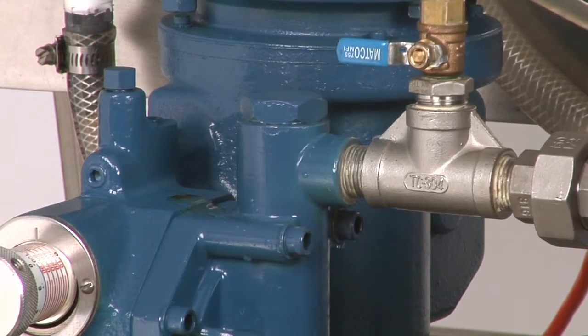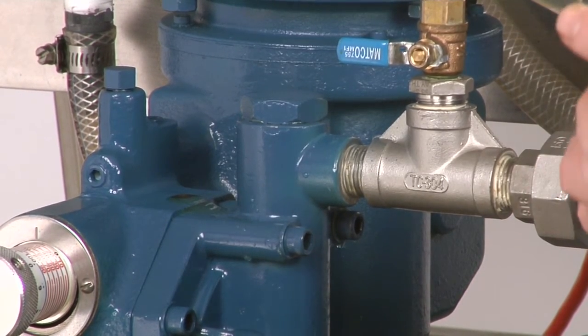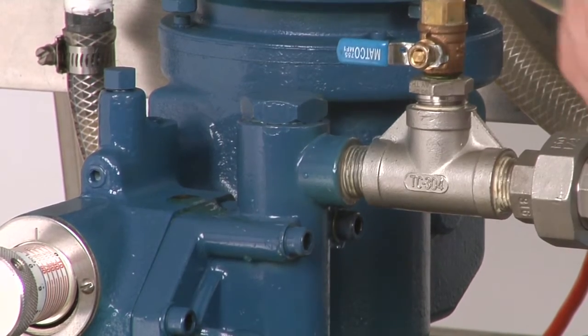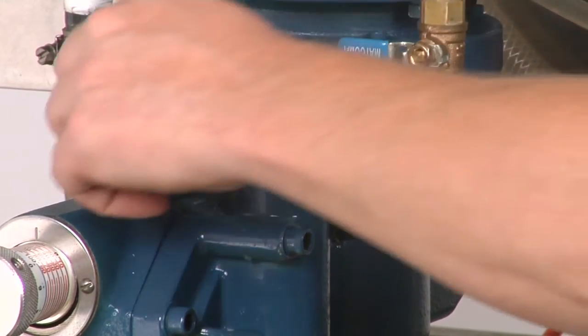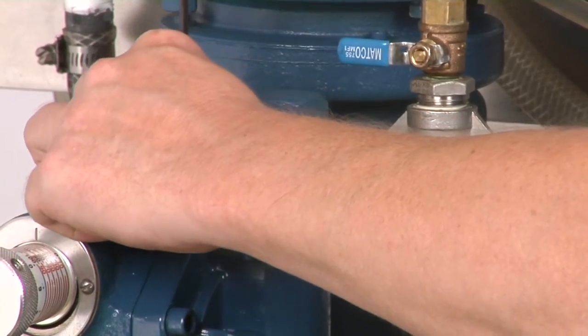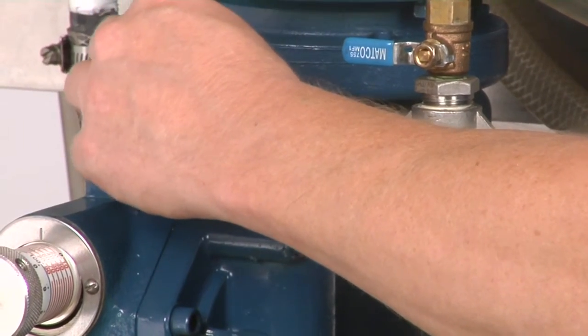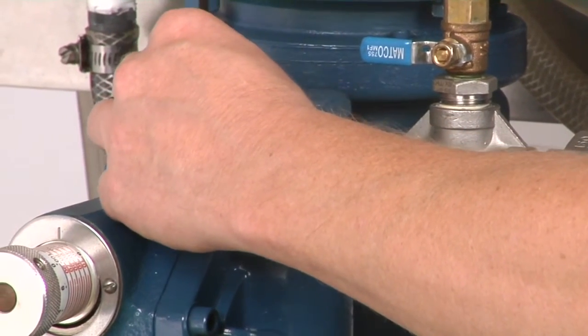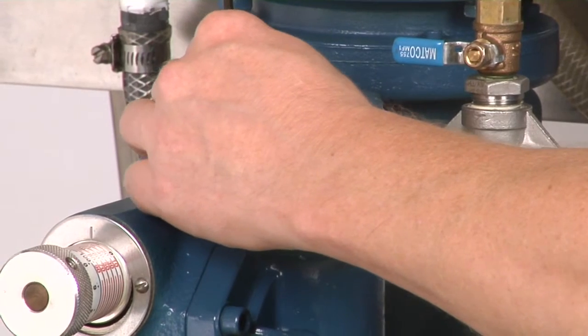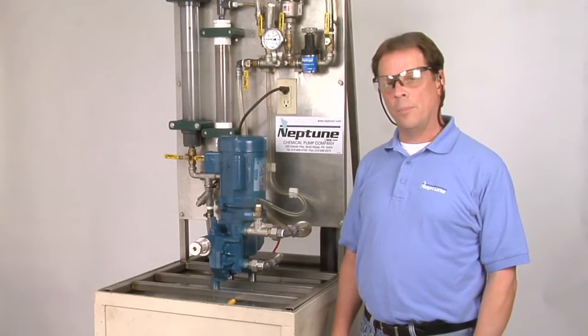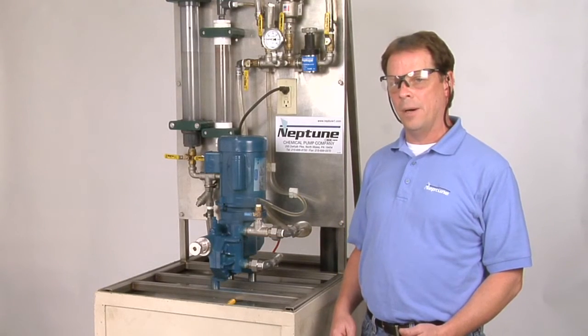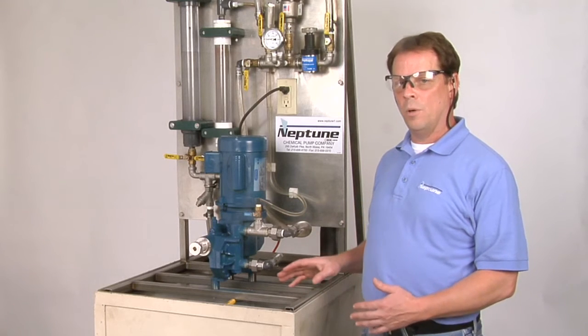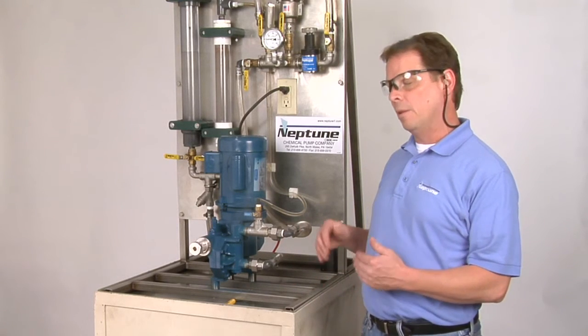This plug is a tapered plug, so there's no need to put Teflon tape or anything like that to seal off the threads. So we're going to put this plug back in and tighten it down. Now we're going to purge the air from the liquid side of the pump. We've already done it from the oil, now we're going to do it from the liquid side.